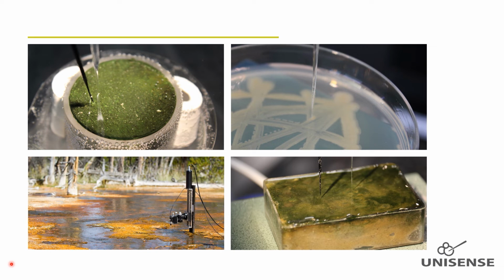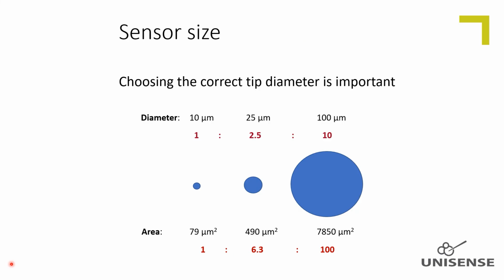This is very important to consider when choosing the right sensor, because the sensor tip blocks free molecular diffusion and therefore has the potential to disturb natural gradients. This potential problem applies to all sensor types, including amperometric, potentiometric and optical microsensors. The smaller the tip is, the less it disturbs the gradients. This slide shows the area of sensors with different tip diameters. As seen, the area of a 100 micrometer tip is 100 times larger than a 10 micrometer tip.